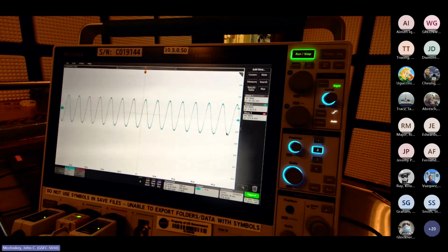Okay, so that's one of the reasons I recommend monitoring the current directly when you're injecting into the unit under test, even if you do the pre-calibration step. Any questions on this before we hook up to the unit under test for the main event?